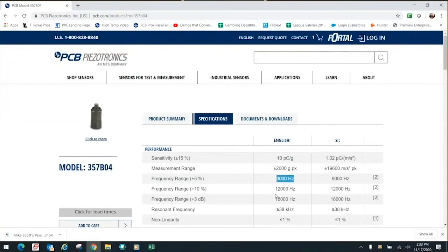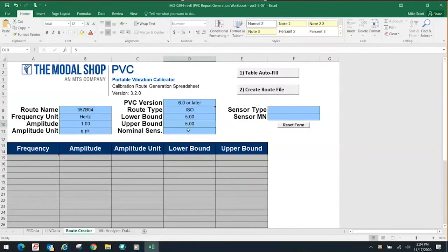It needs to stay within 5% of that value to 9 kilohertz, and then for the ranges above 9 kilohertz to 12 kilohertz, the tolerance is allowed to expand to 10%, and then eventually to 3 dB at 18 kilohertz. Now, our portable vibration calibrator can only go up to 10 kilohertz, so that's what we'll program in this test. So 15% at 100 hertz, 5% to 9K and 10% to 12 kilohertz with a 10 picocoulomb per G nominal sensitivity. So let's go back to the programming.